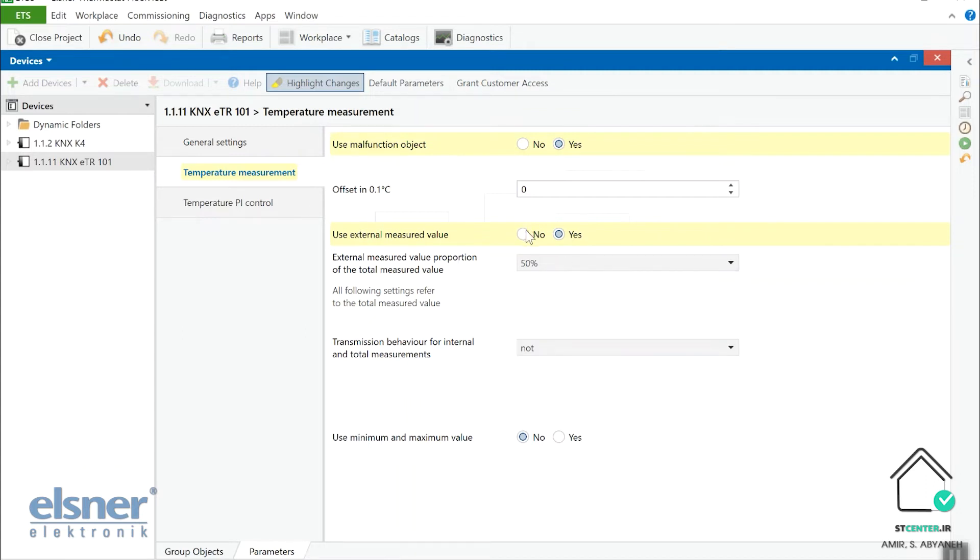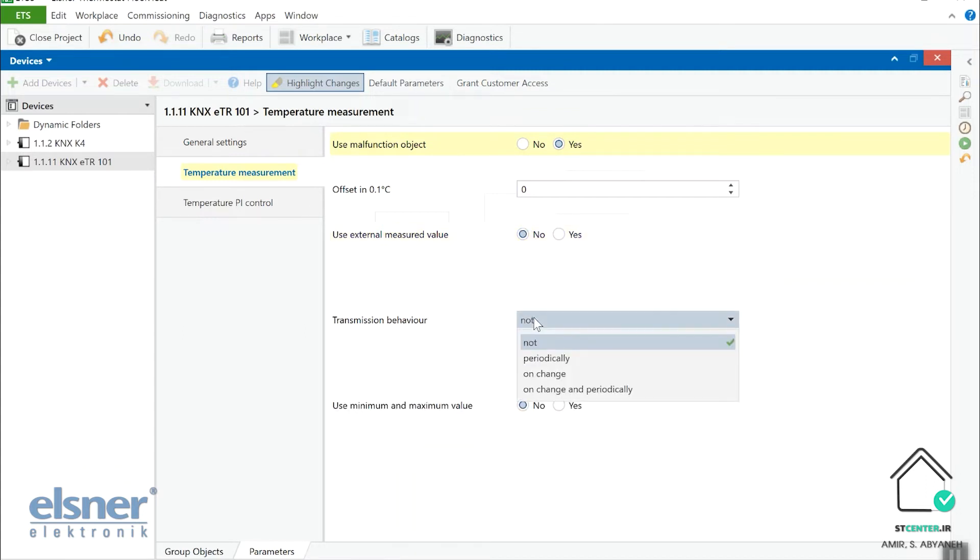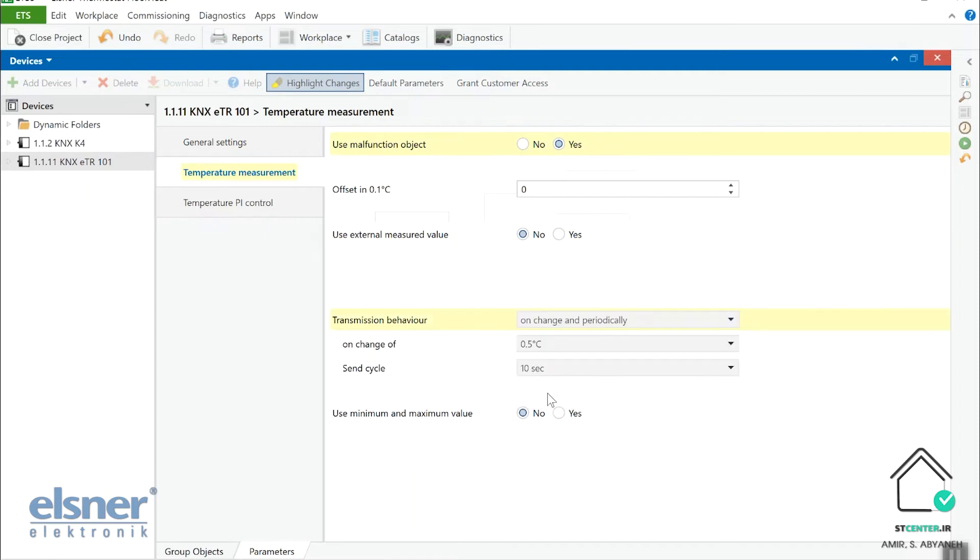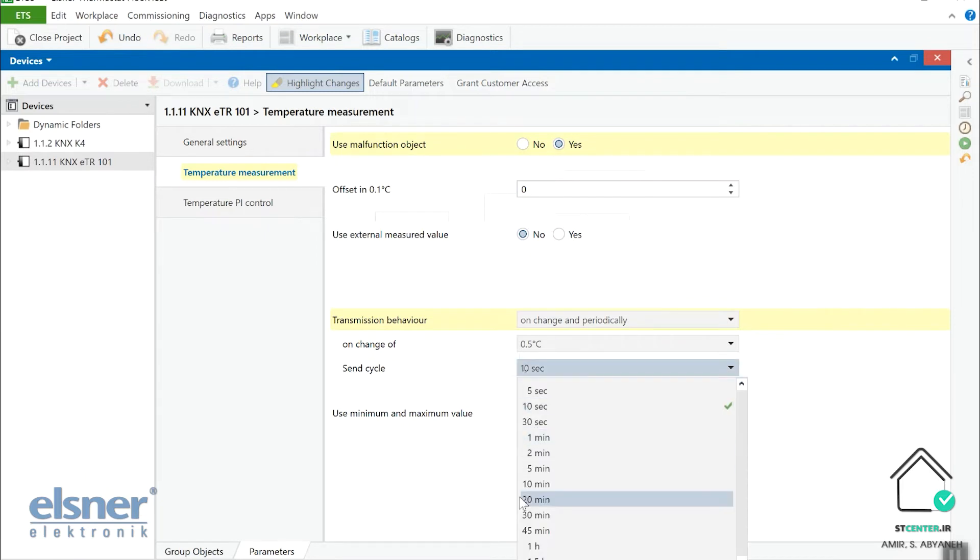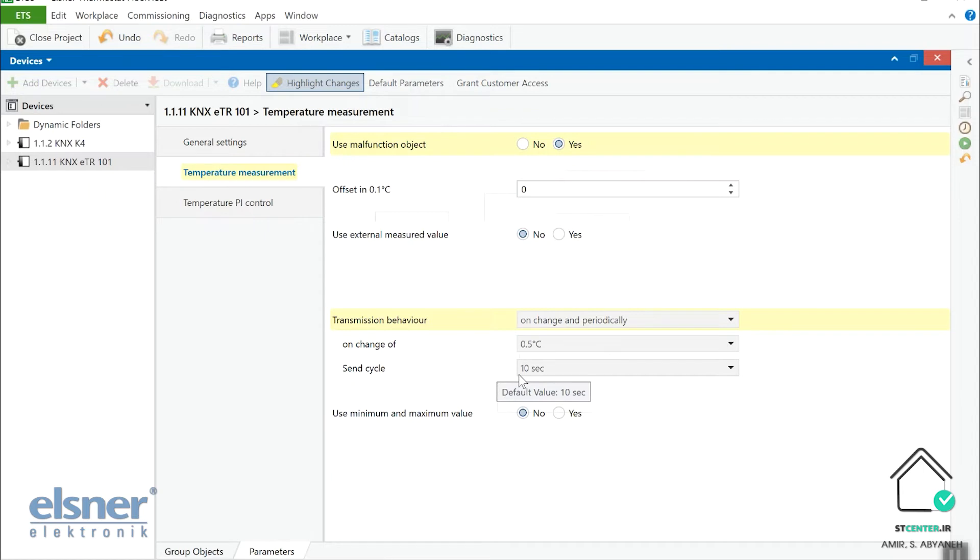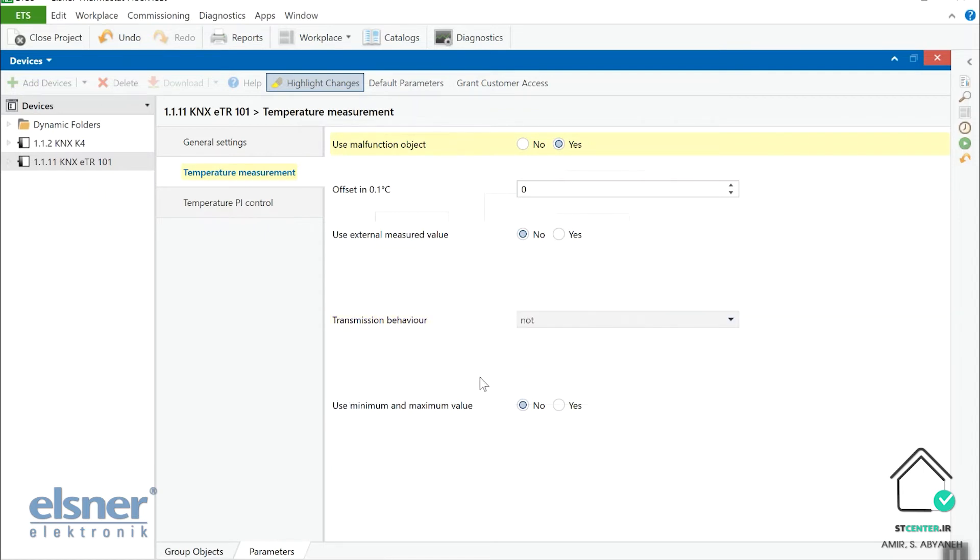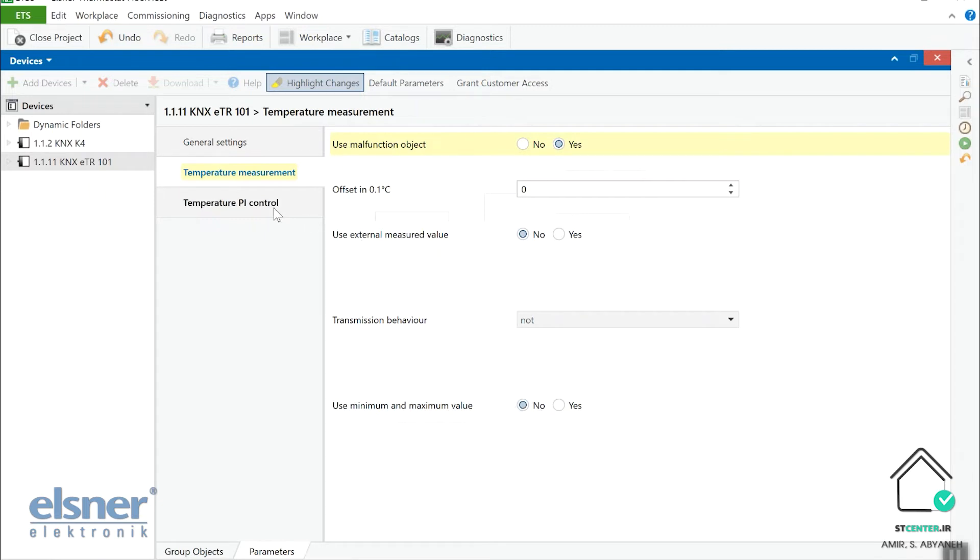In addition, we can tell the transmission behavior. For example, if we put it on change and periodically transmission behavior of the temperature that is read by this thermostat. So we can say if we have any change of more than half a degree, send the temperature again. Okay, or send it cyclically 10 seconds or more. But be careful about sending cyclically because it may increase the traffic of the data. Then we have the possibility for us to have the minimum maximum value of the temperature.